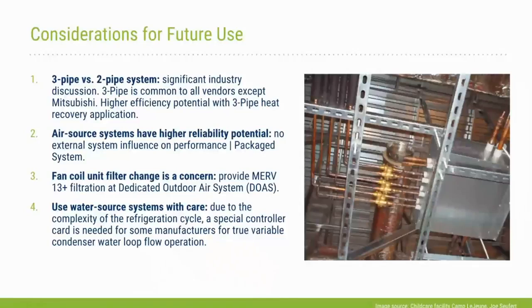Filter change, whether with a VRF system or any sort of fan coil unit or fan-powered system, is a consideration. In this project, we had over 60 distributed fan coil units. So we used care to make sure we address how those filters are changed, but there is still that decentralized component that needs to be taken into account.